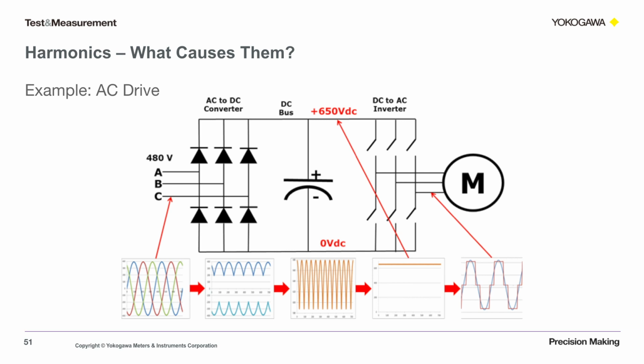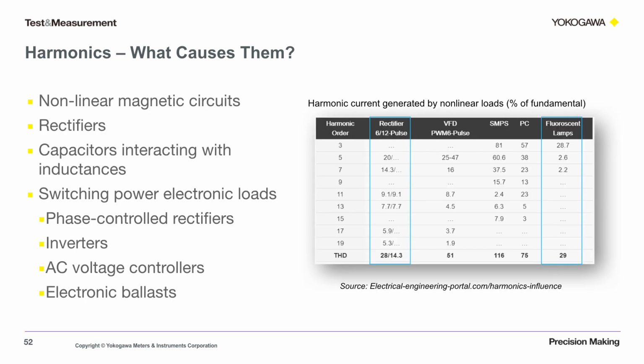An AC motor drive is AC inputs that cuts and chops the waveform. It goes to a capacitive bank and it filters out for DC, and then it goes to a DC to AC inverter stage. So here are a lot of harmonics being introduced due to the chopping and cutting of these waveforms. Just how much distortion is caused by harmonics?